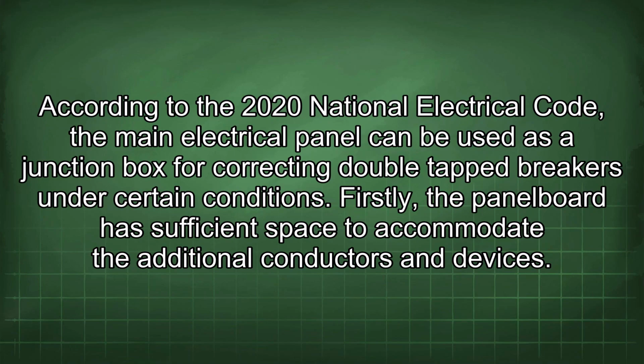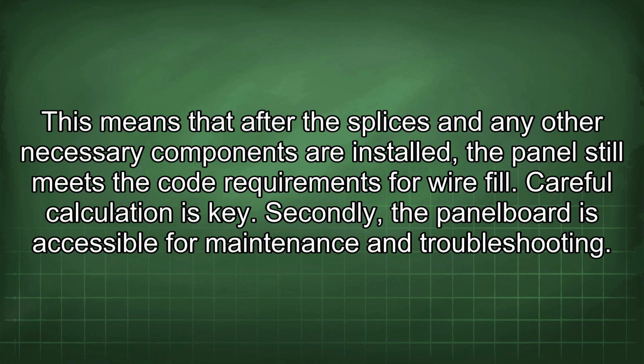According to the 2020 National Electrical Code, the main electrical panel can be used as a junction box for correcting double-tap breakers under certain conditions. Firstly, the panel board has sufficient space to accommodate the additional conductors and devices. This means that after the splices and any other necessary components are installed, the panel still meets the code requirements for wire fill. Careful calculation is key.